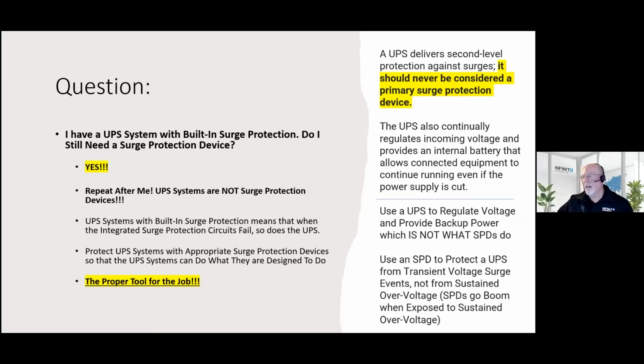Oh, yeah. A lot of people say, well, do you need surge protection at your point of use? Well, I've got a UPS. I don't need it. That's why I put this in here. UPS systems are not surge protectors, but it's got surge protection built into it. No, it's got a surge protection circuit that's just a few components. So you see your UPS, it's big. A surge protector is big, and it's designed to be a surge protector. So you want to put a surge protector in front of a UPS. Let the UPS do its job, because if the UPS's surge components fail, the UPS is dead. So if you want something to be a sacrificial lamb, use the surge protector and let the UPS survive. So you use both. Don't rely on a UPS that has built-in surge protection.